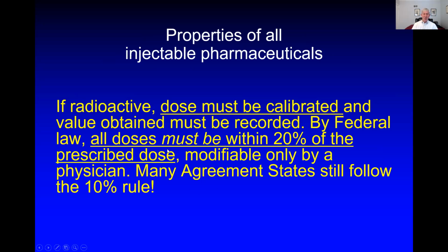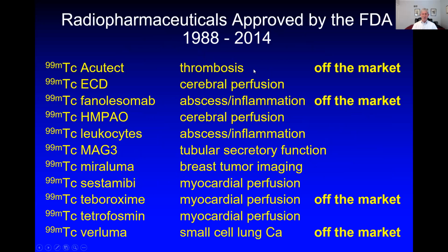And so in our institution, we have chosen the default to be 10%. That's perfectly okay. You can be more restrictive, not more lenient. So remember that number, plus or minus 20%. That is the only percent that you'll deal with in nuclear medicine that is not 10%. Everything else tends to be 10%. We'll learn more about that in the NRC lecture.